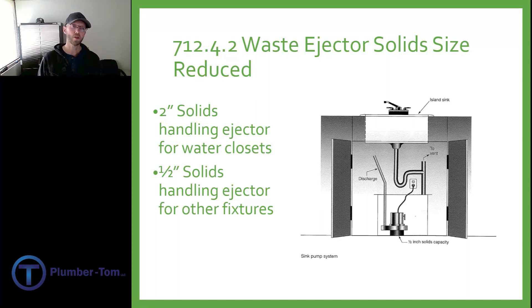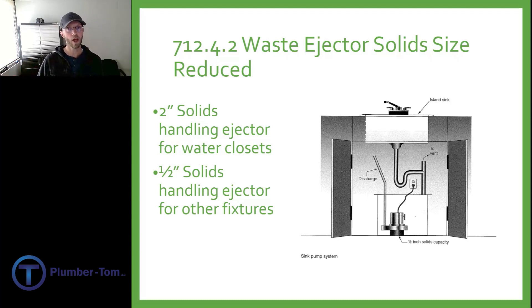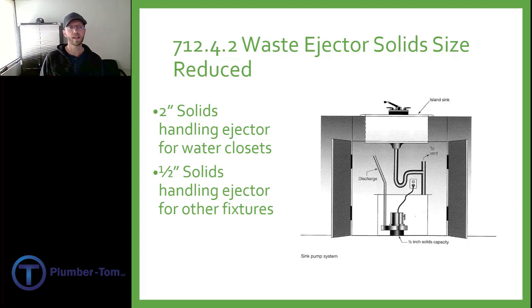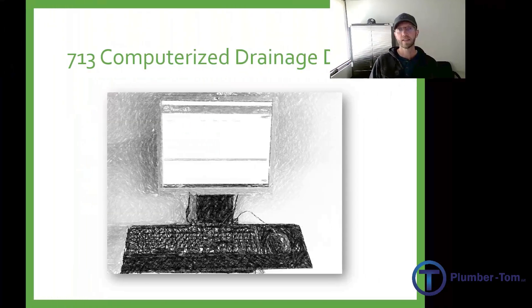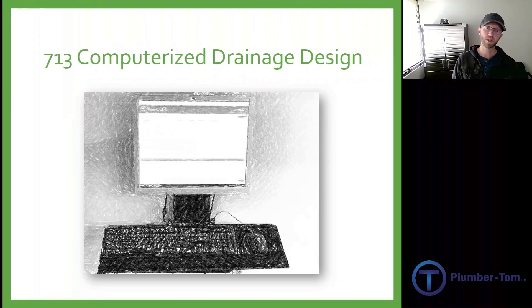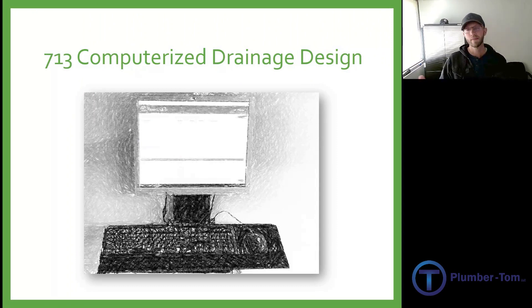712.4.2 talks about waste ejector solids size, stating that anything receiving waste from a toilet must be able to handle up to two-inch solids. If it's not a toilet — like a sink — the requirement is half-inch solids. Section 713 covers computerized drainage design and basically states that any sizing done by computers would have to be approved.